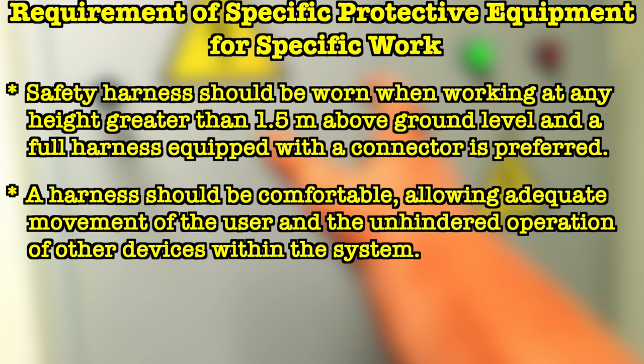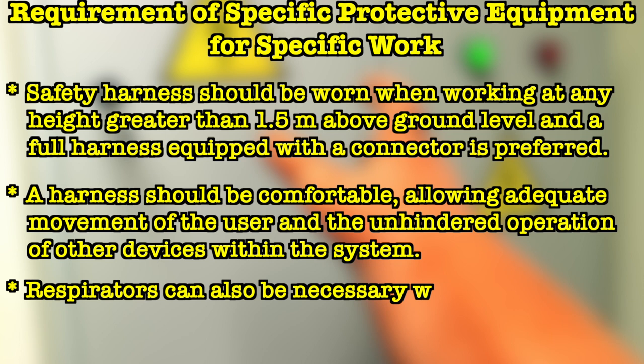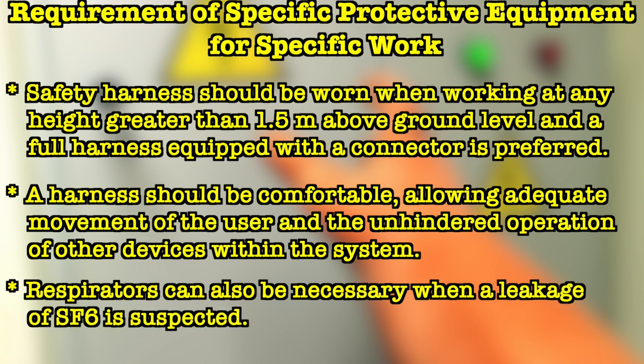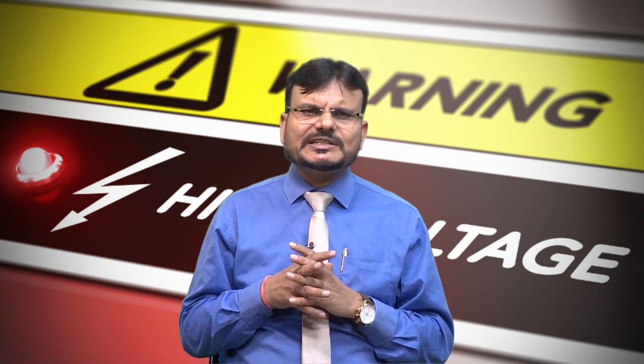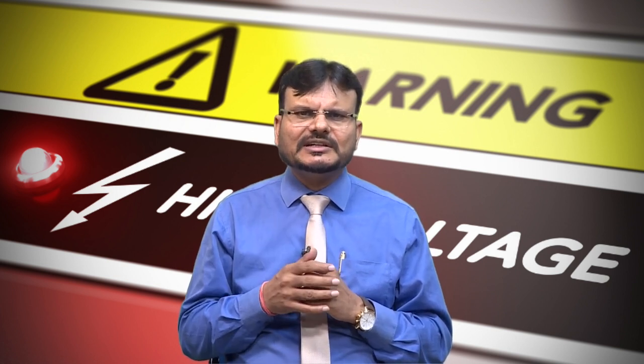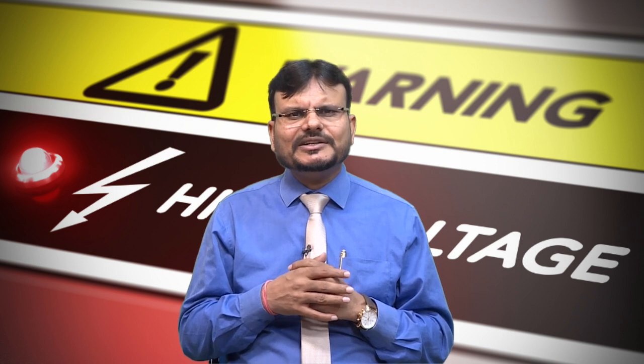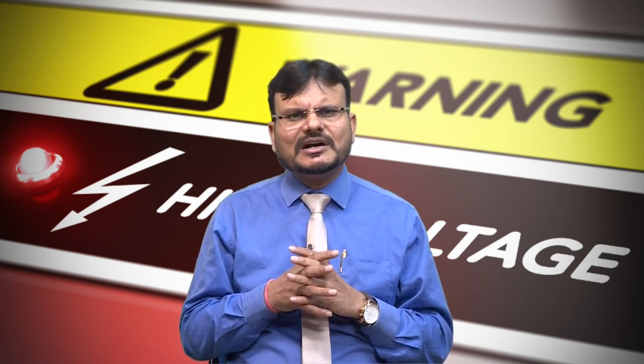Harnesses should be comfortable, allowing adequate movement and unhindered operation of other devices. Depending on working conditions, a seat harness may be necessary — it has lateral and central attachment points and is designed primarily for work in suspension. Respirators can also be necessary when leakage of SF6 (sulfur hexafluoride) is suspected. Although SF6 is not toxic, it degrades under the heat of arcing to hazardous gases. When performing energized work or switching operations, insulated gloves and dielectric shoes are required, and gloves must be tested and suitable for the working voltage.